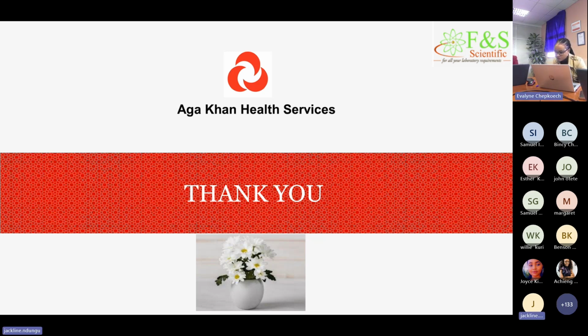I have finished. She's also asked if there's an issue if all control points are on the mean. No, I don't think there's an issue, because when you look at hematology analyzers, most of the time, unless the equipment has a problem, most of the analytes will be at the mean. I don't think that's a problem. It's like asking, if I'm perfect, do I have a problem?